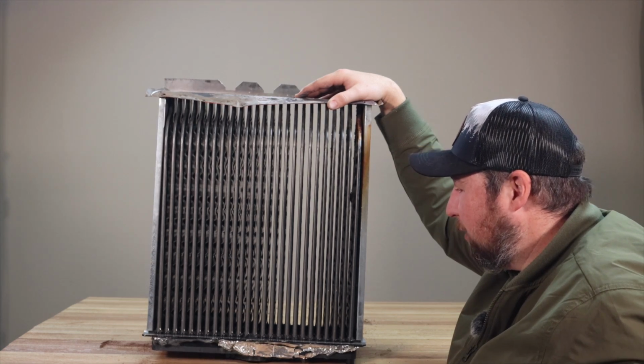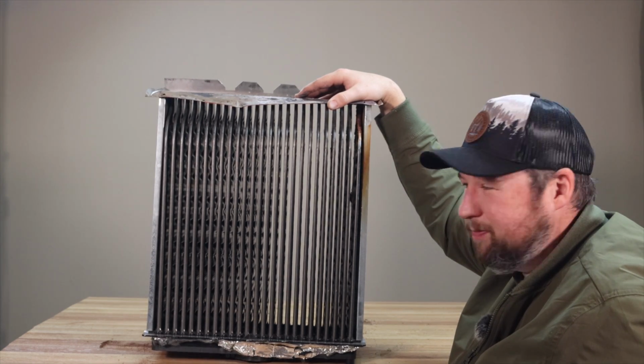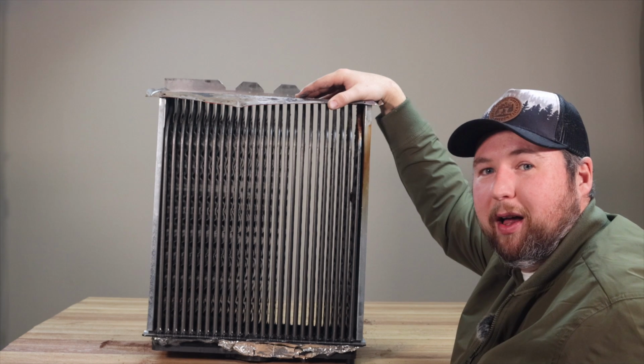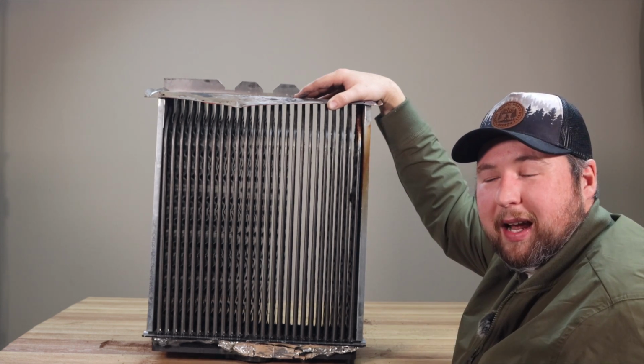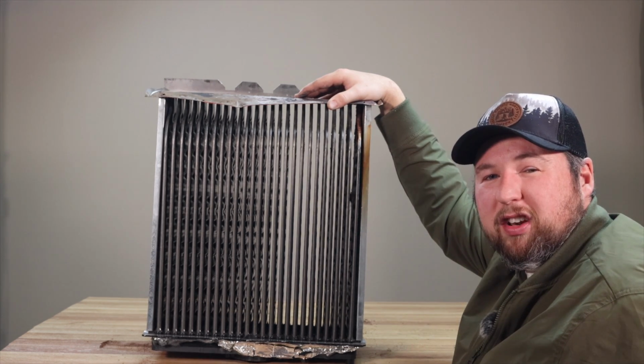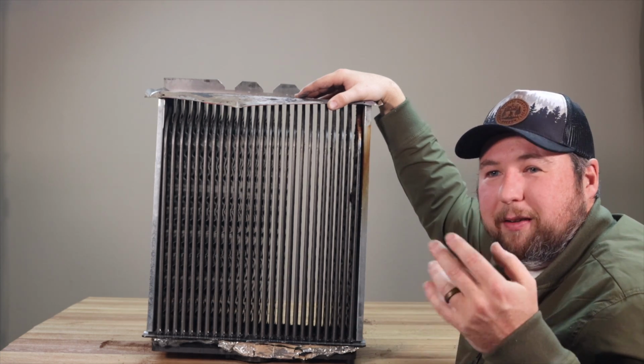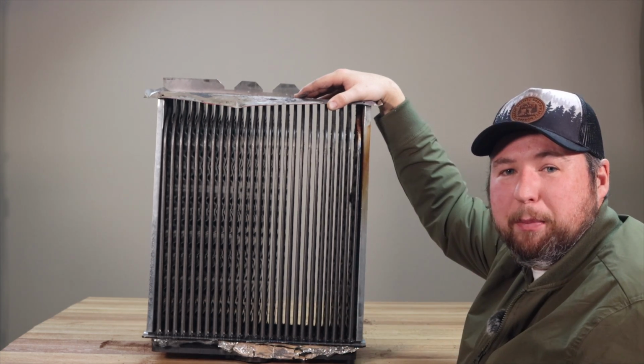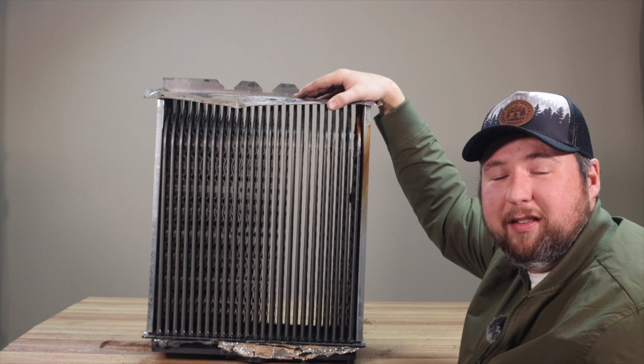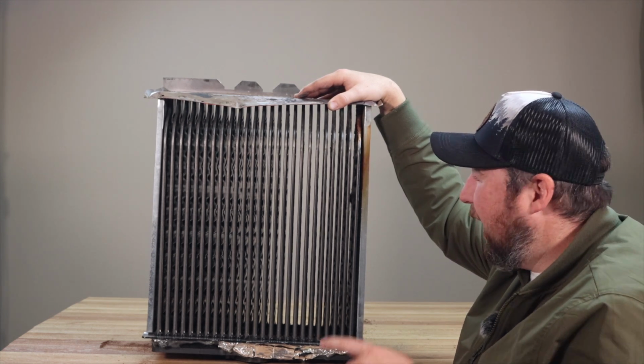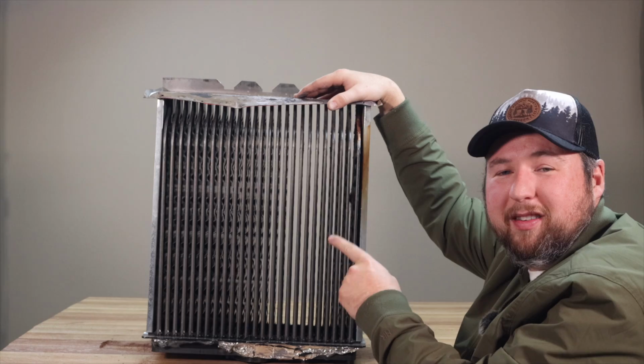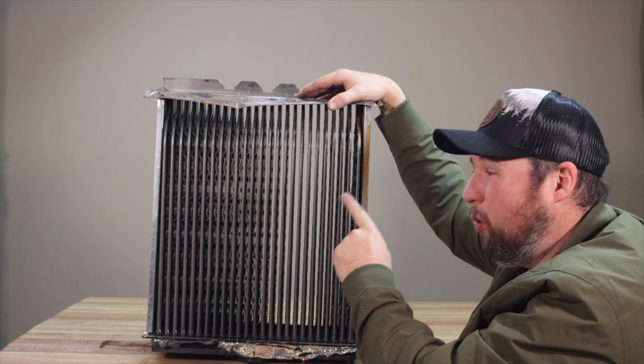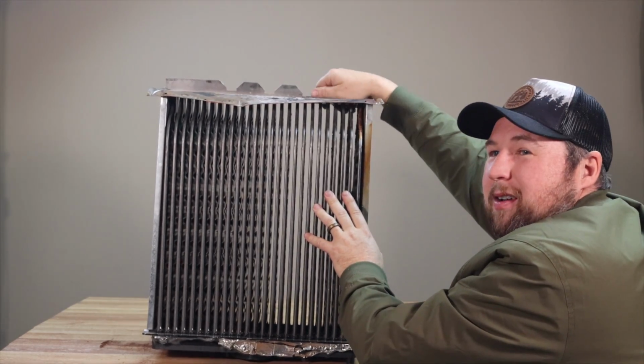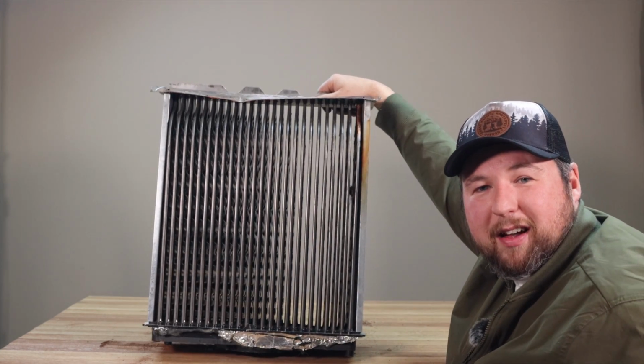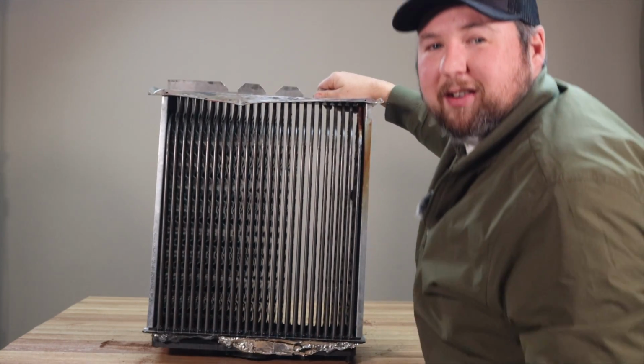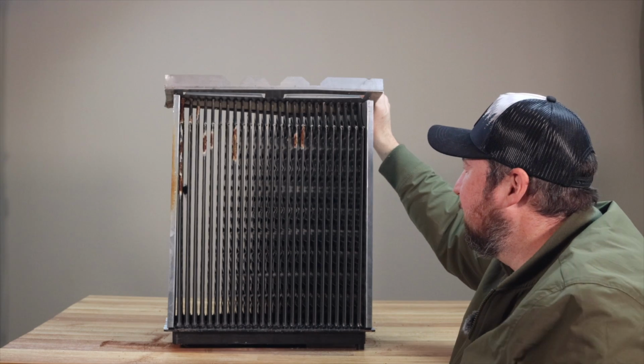As far as heat transfer goes, when they're brand new, they're great. They work really well, but they have problems. And this is one of the reasons why I don't like 90% heat exchangers. I don't like the fact that they condensate. I don't like the fact that you have water, because if you have improper combustion, it produces a lot of nasty stuff which gets stuck in said water and gets stuck in the secondary heat exchanger, because these things never drain 100%. There's always some water in there. So what happens if you have acidic stuff in the water sitting in this heat exchanger? You get secondary heat exchanger rot.